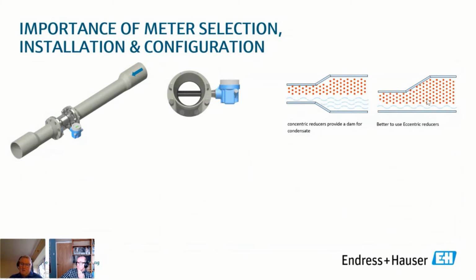So instead we use an eccentric reducer like this one. You can see the eccentric reducer here, with whatever straight lengths it needs, from 6 to 10 to 15, depending on the type of technology. Then the meter, then back out again. We've even rotated the meter 90 degrees here, so you can see now there's nothing stopping the flow of condensate through this meter. Rotating the meter using eccentric reducers is something we do all the time with steam measurement, just to ensure that condensate can freely pass the meter and drain.